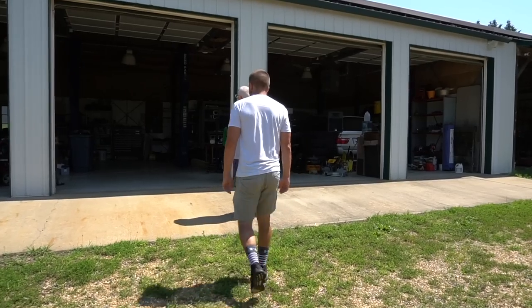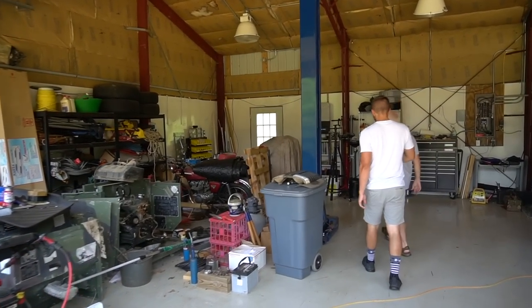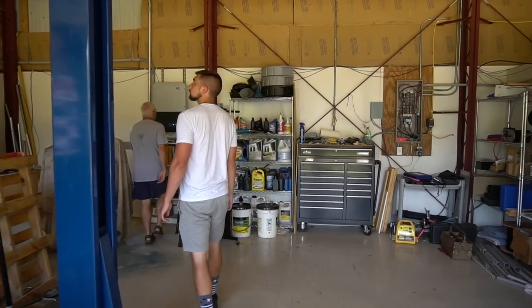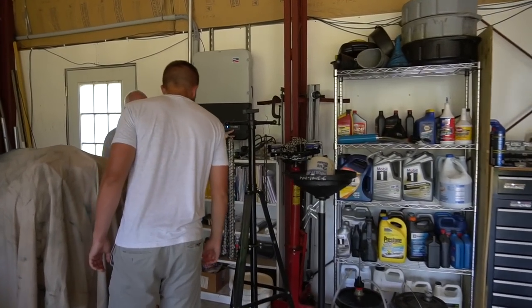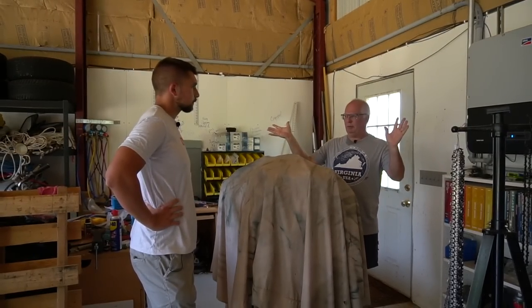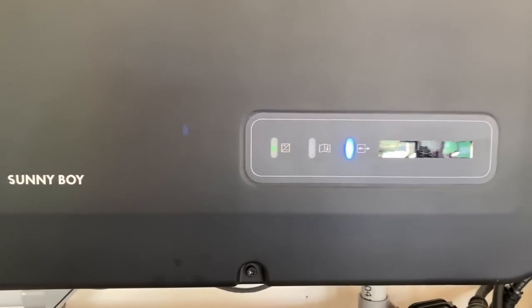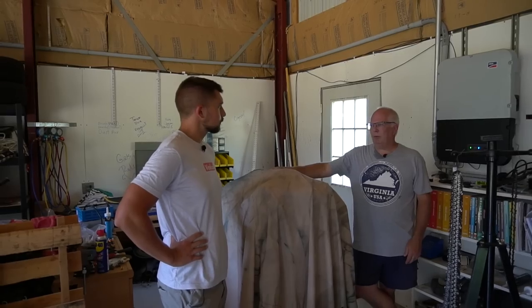In here is that second Sunny Boy mounted inside — this one captures the DC power coming from the pole barn. This one is already at 6,500 watts, so it's going to max out within the next hour or so and stay there until probably three or four this afternoon. So maximum solar output is like 12 to 3? Being that it's daylight savings time, the sun is highest at 1 PM. Not all the panels are aligned exactly the same toward the sun, so they don't all peak at the exact same time. In summertime I'd say from about 11 AM till about 3 PM is when I produce the most kilowatt hours.